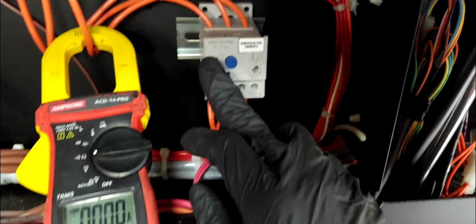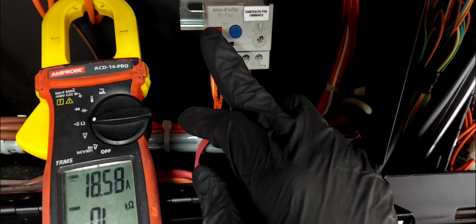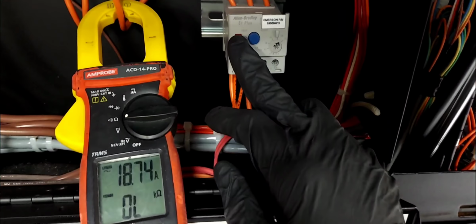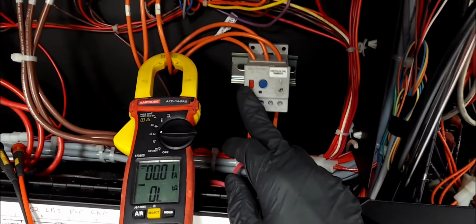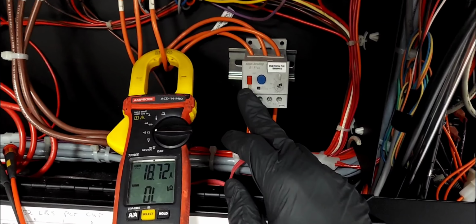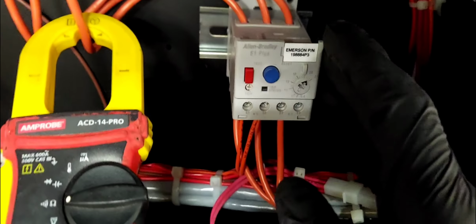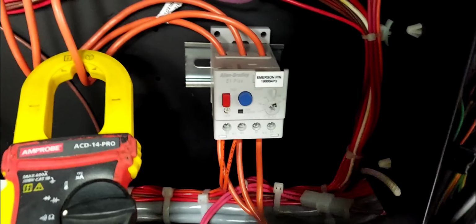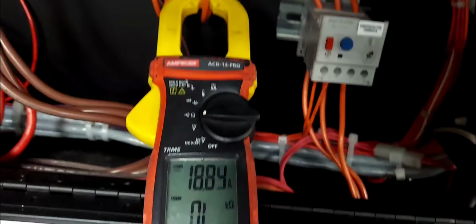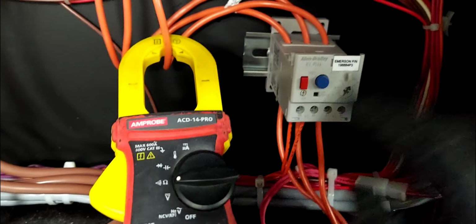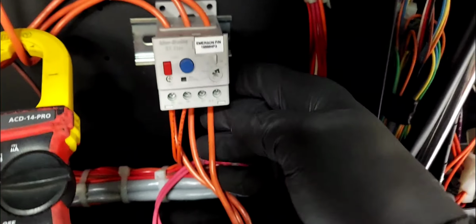I hit the test button right here. Start it again. I think this thing may be faulty. Has to be. Because again, the set point is all the way at 24, 25 amps and we're only running at 18. So my main fuses are good, intact. Yeah, I'm gonna say that this thing must be faulty. It has to be faulty.